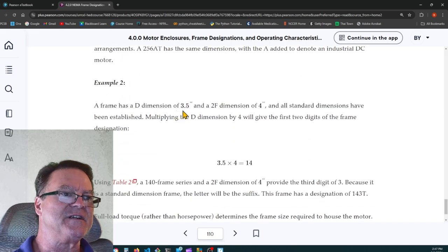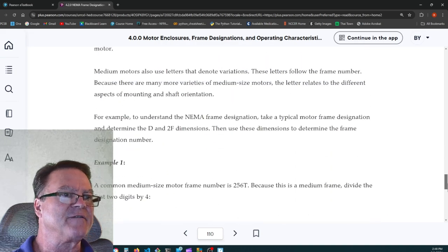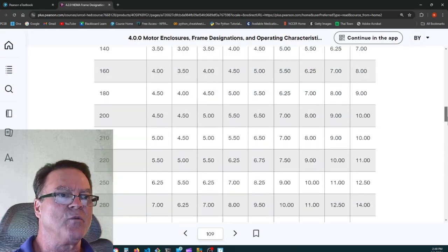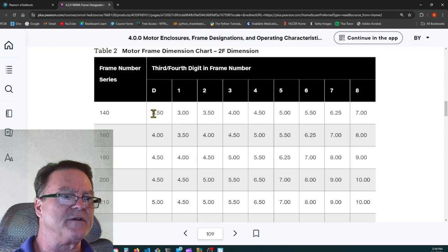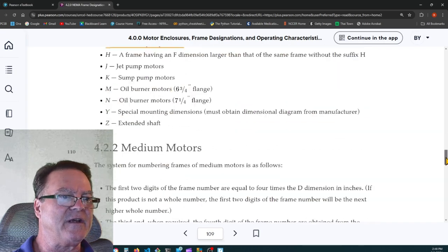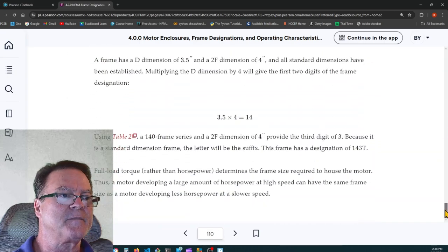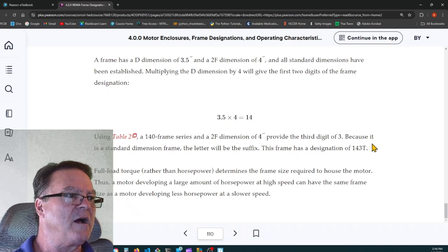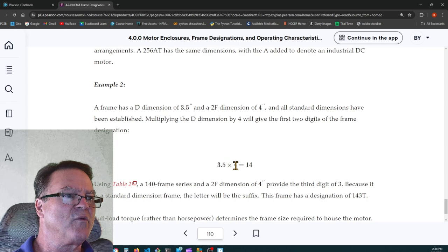So, a frame has a D dimension of 3.5 inches and a 2F dimension of 4 inches. So 3.5 and 4, if we went up to this chart, we could find the 3.5 is a 140 series and 4 is 3, so the number should be 143, 143T. So let's see what they've got. Because it's a standard dimension frame, the letter will be the suffix. The frame has a designation of 143T. So the 3.5 times 4 is 14, and then the 140 frame series, a 2F dimension of 4 inches is provided.